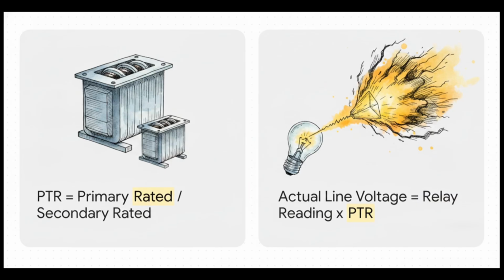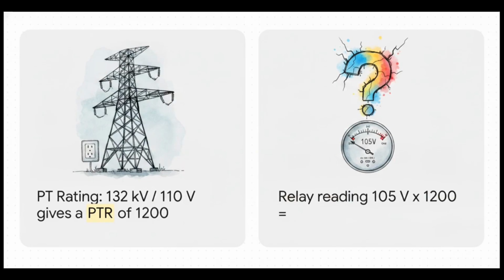It's the exact same logic, but here we use a potential transformer ratio, or PTR, to translate the voltage down. The PTR is the rated primary voltage divided by the rated secondary voltage. The actual line voltage is calculated by taking the relay's reading and multiplying it by that PTR. Let's run the numbers one more time. Imagine a substation with a PT rated for 132 kilovolts over 110 volts. That yields a PTR of 1200.